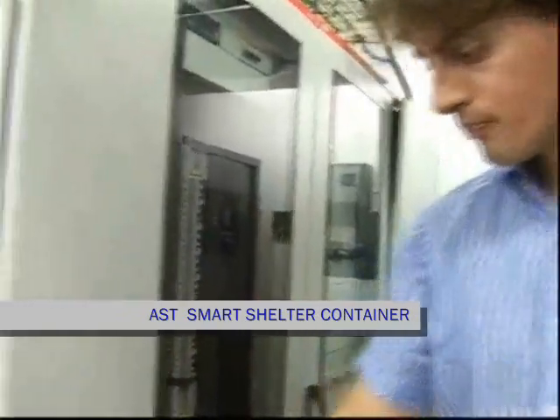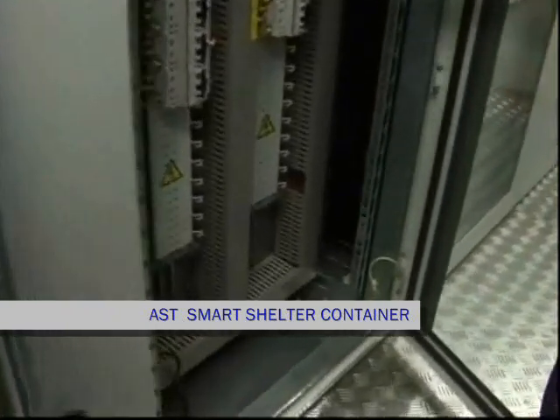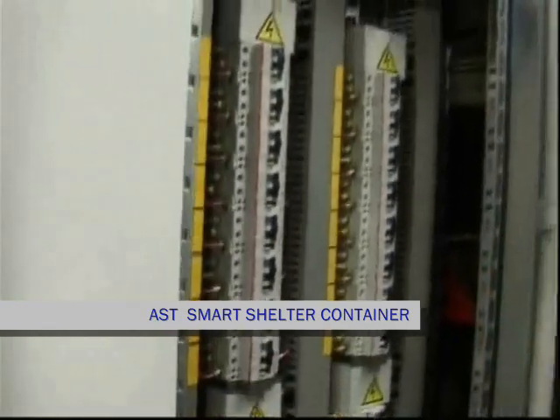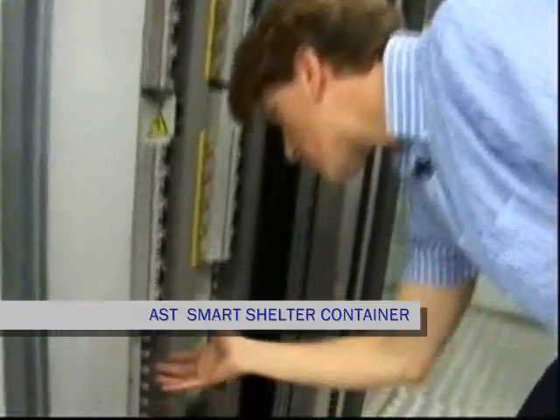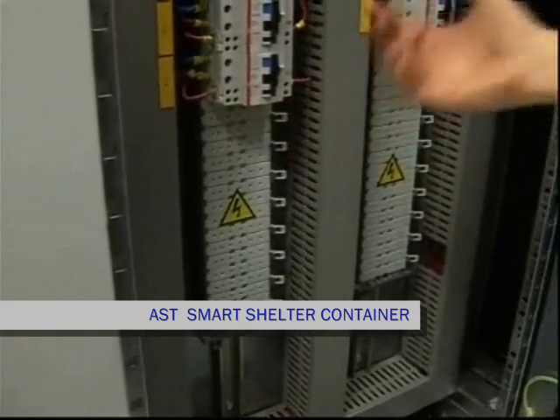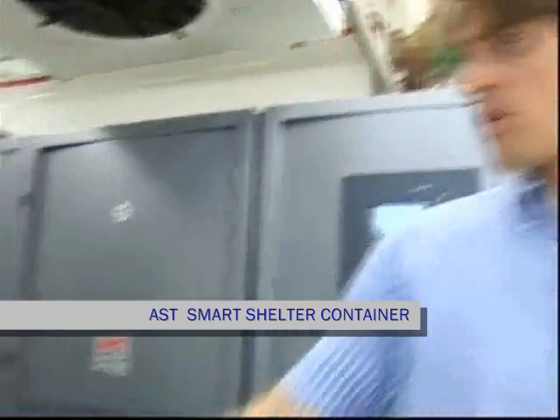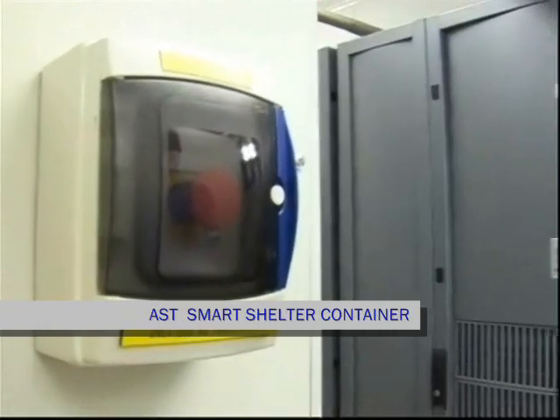And then finally we go into the protections for our servers, which are hot swappable. Therefore, this switchboard has been designed and built in order to allow easy future expansion by providing additional space for these hot swappable units, in order to allow future growth, or maybe to expand our density from 8 kilowatts to higher density needs. Finally, we have assembled on this unit the EPO, the emergency power off button, in order to comply with local regulations as well. So this is more or less the general overview of this specific unit. If you need more information, I recommend you access www.ast-global.com.